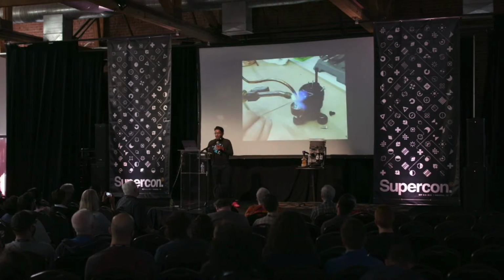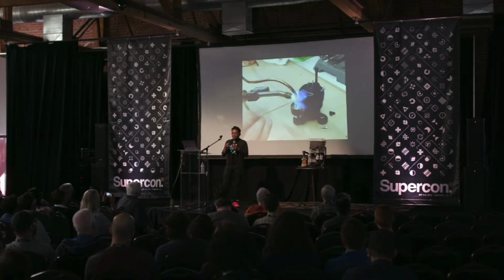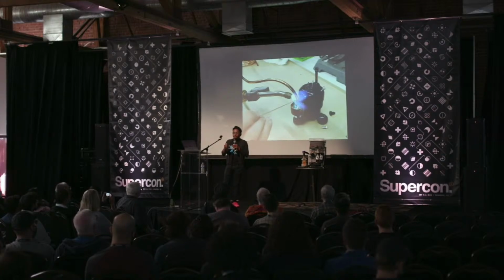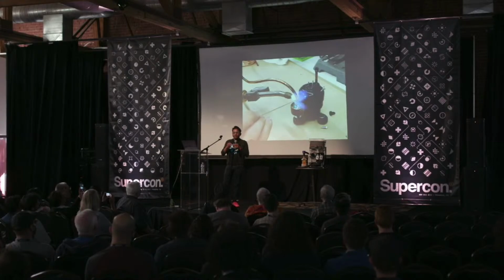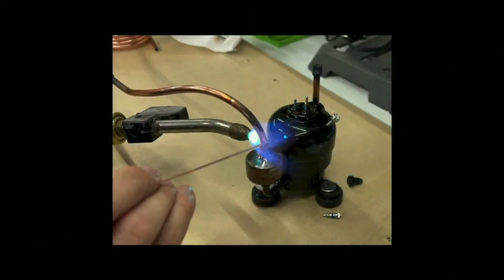The next step is to braze the components together. Brazing is similar to soldering - it can connect dissimilar metals together. Using high silver brazing wire, you can connect copper to stainless steel, for example. You'll want to make sure to use a wet paper towel to protect the components that are heat sensitive. And you can use an oxyacetylene torch for finer control, but you can get the same results from a propane torch as well.